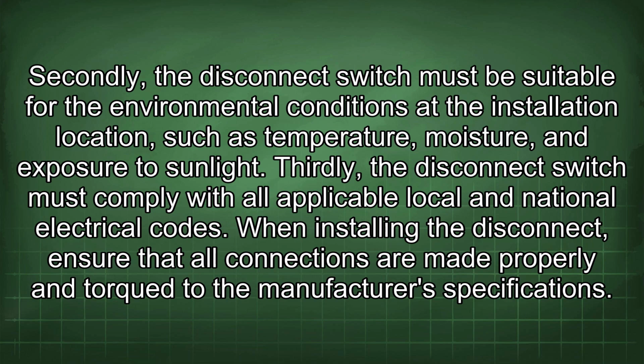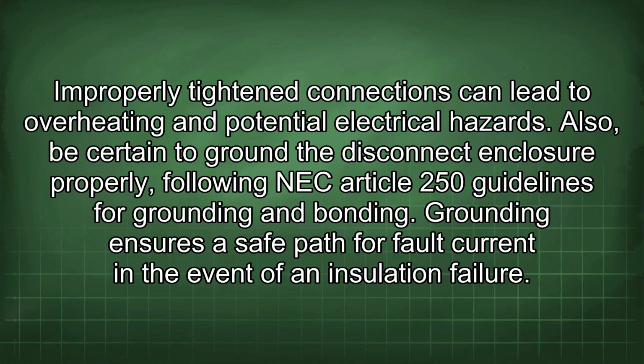When installing the disconnect, ensure that all connections are made properly and torqued to the manufacturer's specifications. Improperly tightened connections can lead to overheating and potential electrical hazards. Also, be certain to ground the disconnect enclosure properly following NEC Article 250 guidelines for grounding and bonding. Grounding ensures a safe path for fault current in the event of an insulation failure.